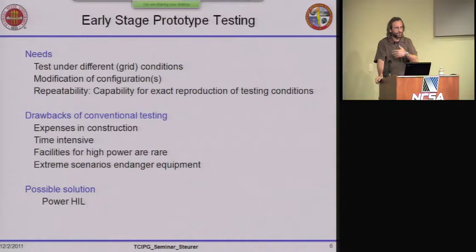Let me give a few definitions. We deal with controller hardware in the loop, CHIL, and power hardware in the loop, PHIL. The major difference: in controller hardware in the loop simulations, a simulation piece executes in real time, interacting with a controller device or protection relay, like a microcontroller that has to control a piece of power hardware. Typically it exchanges low-level signals at the plus or minus 15 volt level, a couple milliamps, with the simulated part of the system. So the interfaces are primarily A to D converters, or in some cases direct digital communication channels.